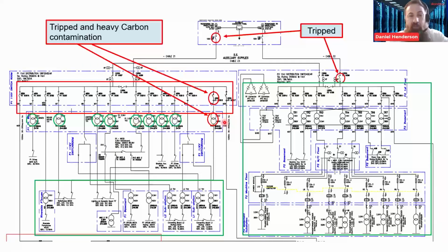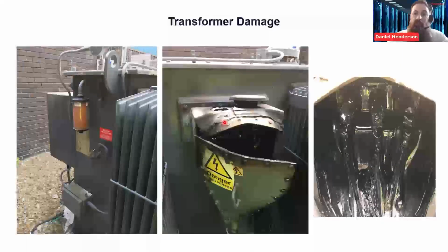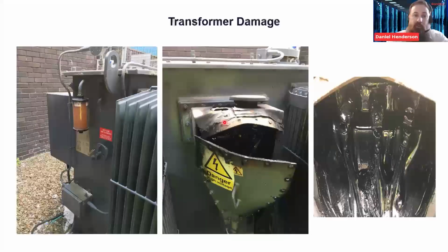So we've got power back to site, and now we're into the stage where we need to start understanding what's gone wrong. So just for some context, this is what was found. So this is the transformer itself. This is the HV junction box. So this is 11 kV. You'll see that all of the studs on the junction box have completely torn away. On top, you'll see between two phases, you've got a hole about 2.5 inch diameter between the two phases. That's about 5 mil mild steel, that junction box. So quite a lot of heat to actually burn that through. And then this is what's left of the junction box.